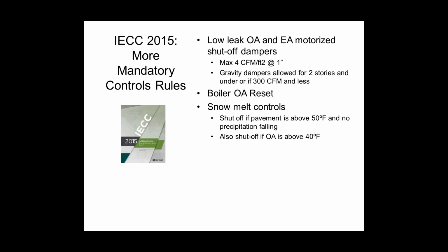If you decide to put snow melt systems in, you have to have different controls on there to prevent it from wasting heat. So you have to shut off the system if the pavement gets above 50 degrees. So you have to have a pavement sensor. That requires some thought on your part because you have to install that before the concrete is poured. You can't do this after the fact when you hire the controls guy. You have to have that sensor put in when the person pouring the concrete is there.